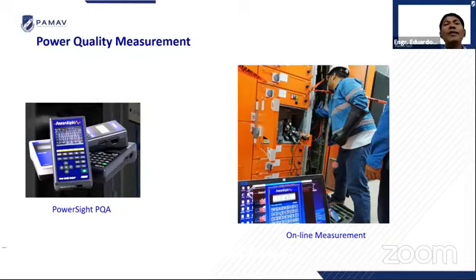And how can we record? We have a recording time for the power quality. Sometimes we do a spot measurement. With a spot measurement, at that time you can read what your power quality indication is. But if your customer wants 24 hours or 1 week, it can be done, as long as your device can hold much longer data, meaning it has more gigabytes on the hard drive of your power quality device, so it can measure.